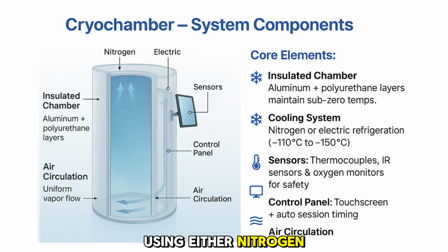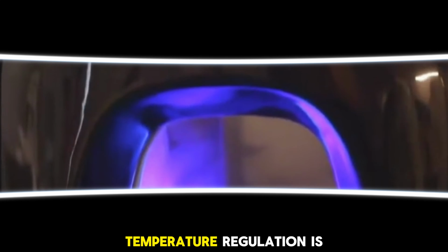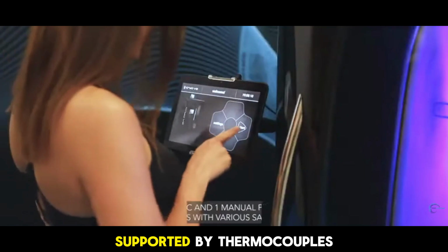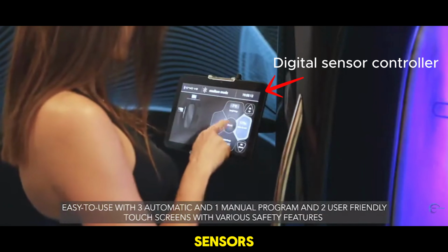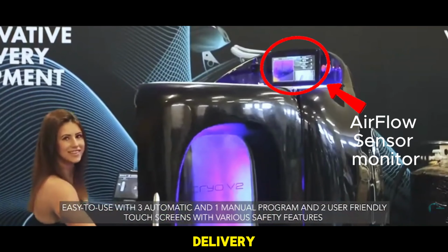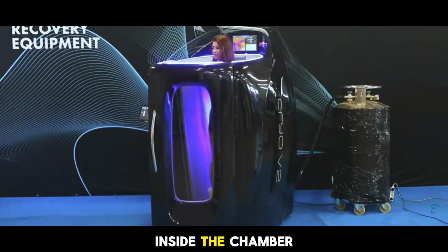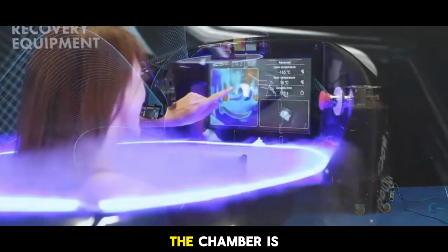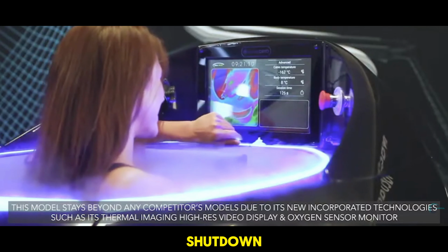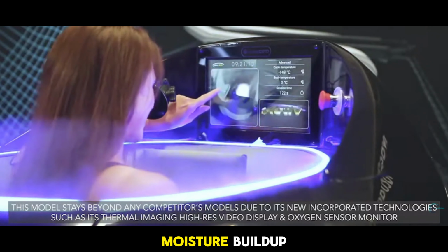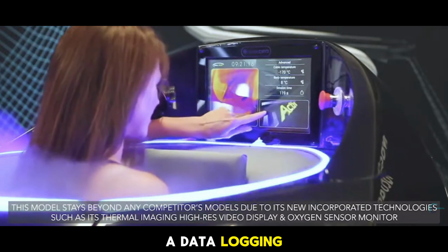Cooling is achieved using either nitrogen or electric refrigeration, with temperatures ranging from -110 to -150 degrees Celsius. Thermocouples and infrared sensors monitor internal conditions, while a touchscreen control panel manages session timing. Air circulation ensures uniform cold distribution throughout the chamber. Temperature regulation is maintained by a PID controller, supported by thermocouples, RTDs, and infrared sensors. Airflow sensors confirm adequate cold air delivery, and oxygen sensors monitor breathable levels inside the chamber. A door interlock prevents operation when the chamber is open, and an emergency stop allows immediate shutdown. Humidity sensors detect moisture buildup, and session parameters are recorded through a data logging system.